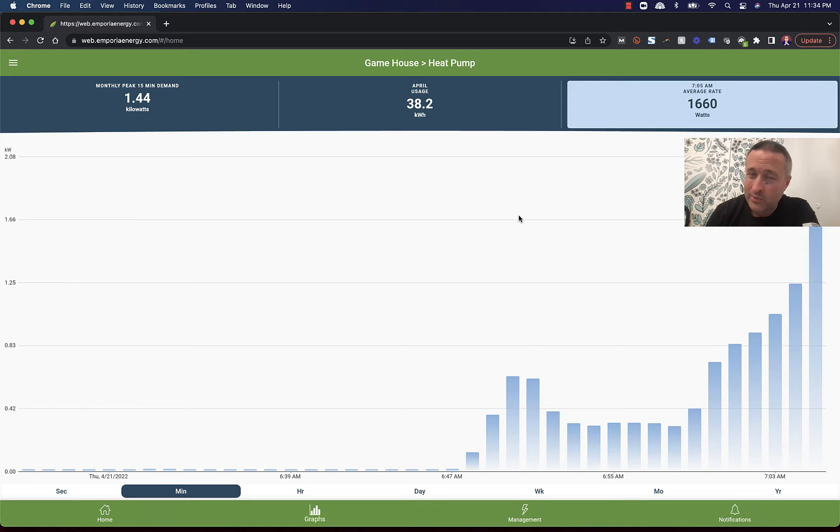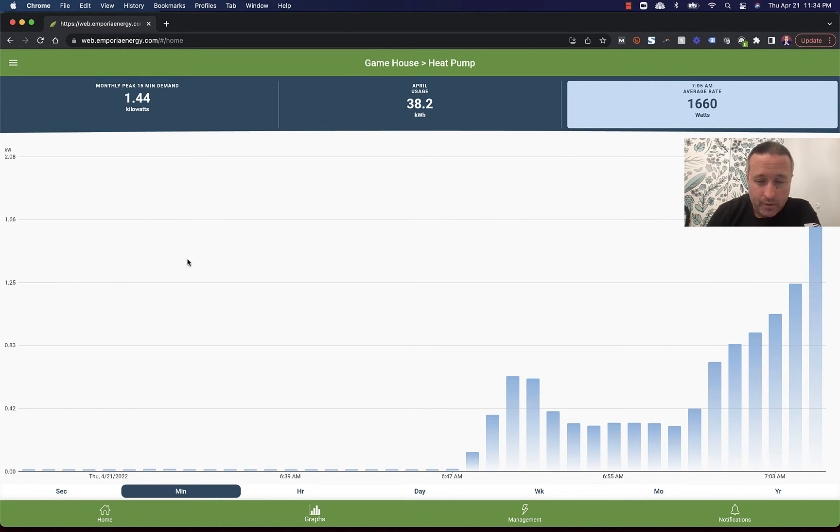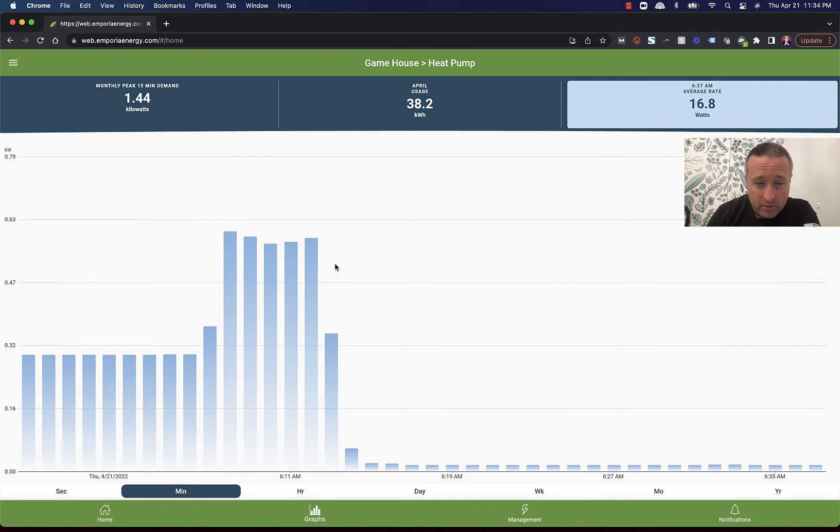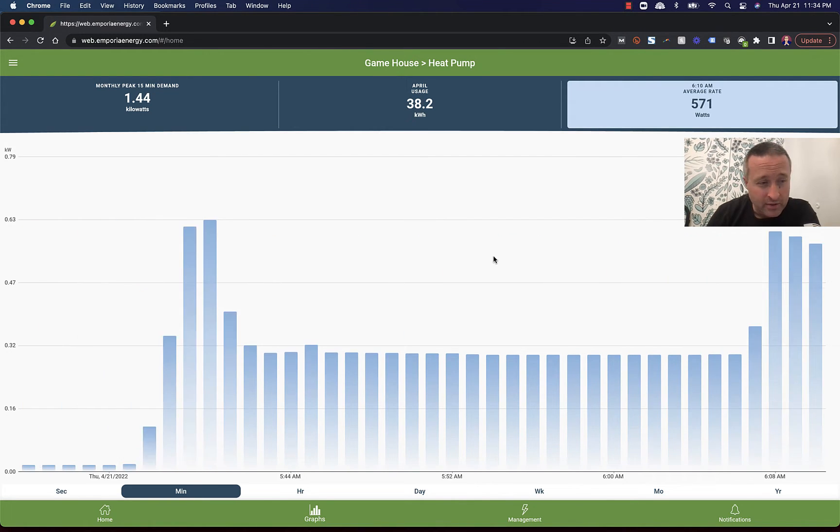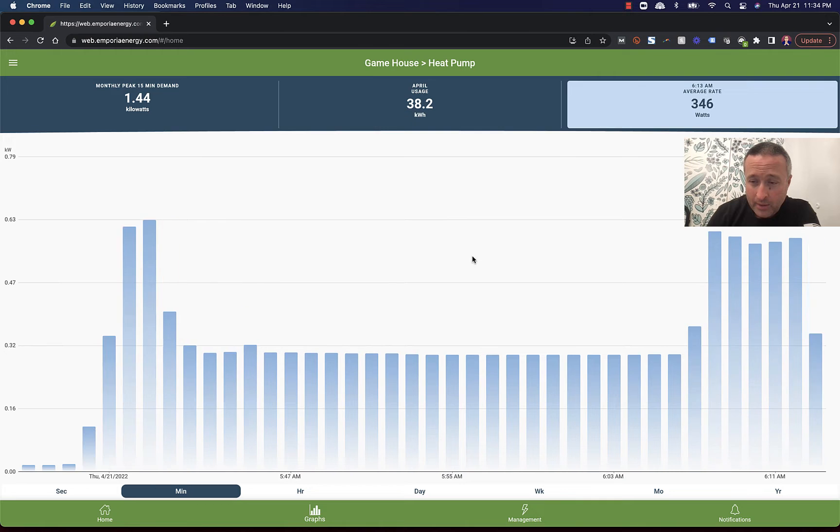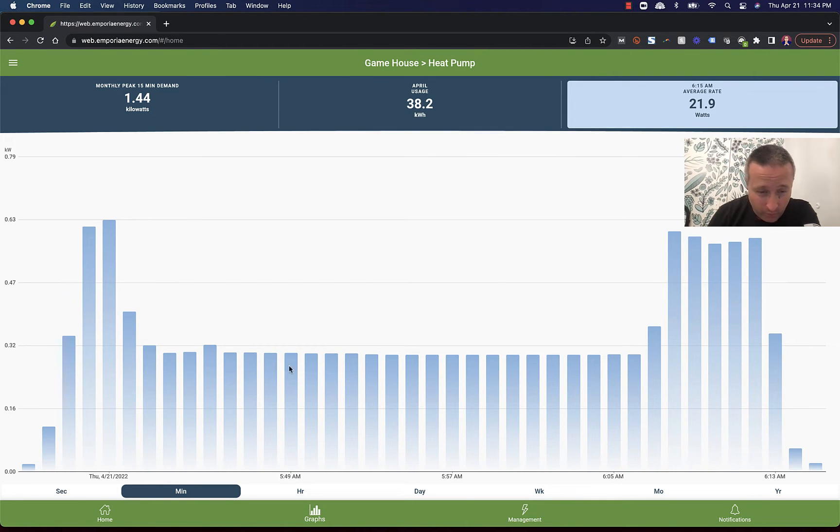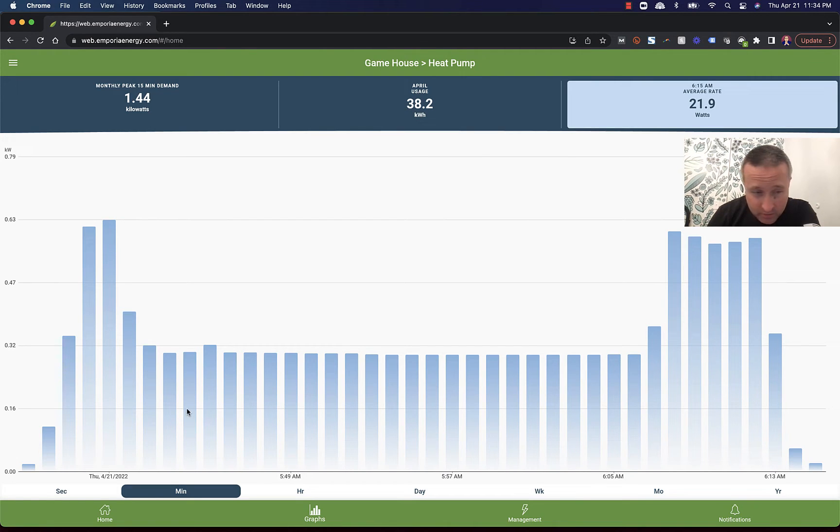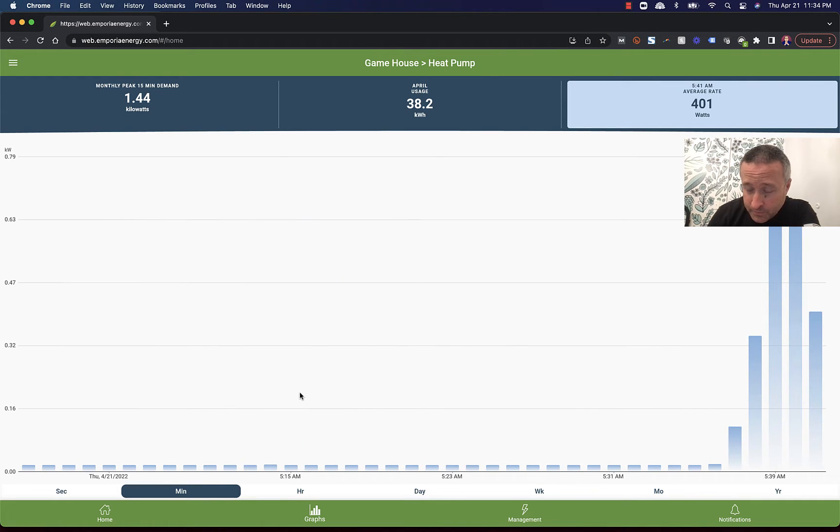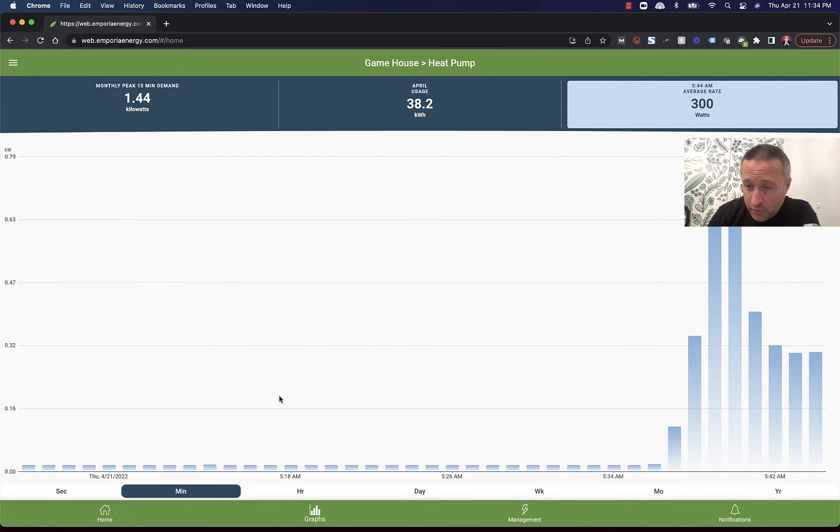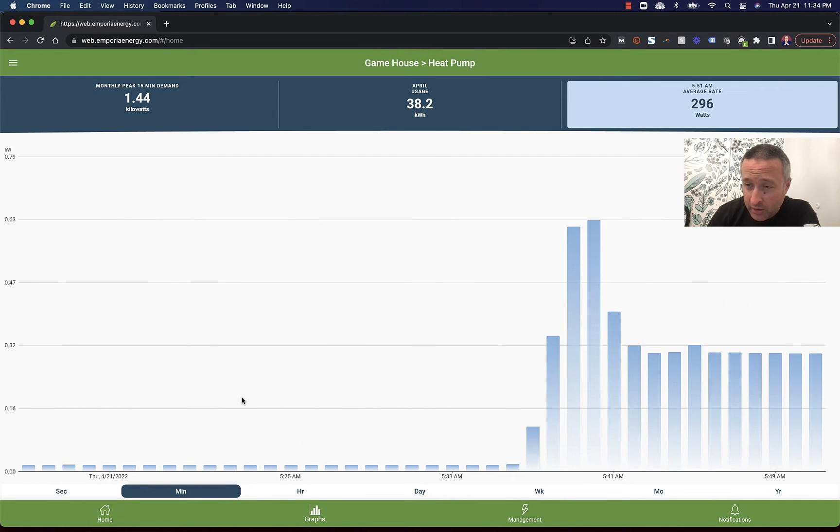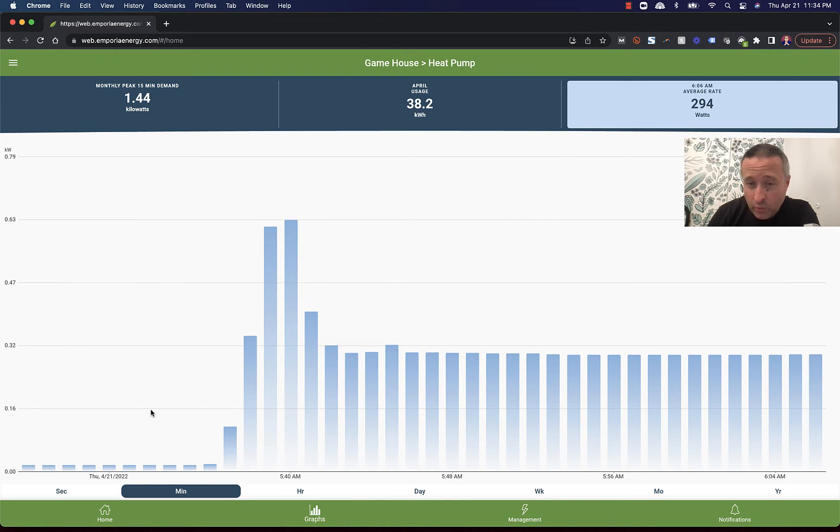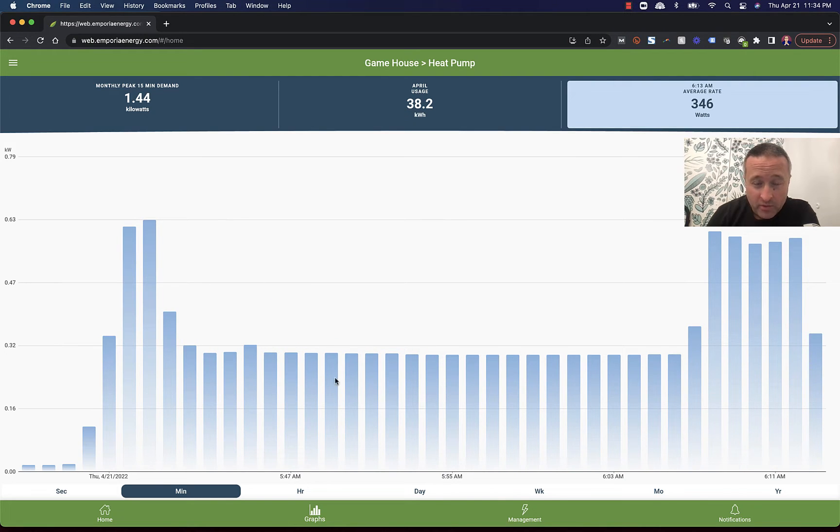It's a one and a half ton unit. So it can do a little bit more than one and a half tons, which makes sense. It's not really a one and a half ton compressor. It's got more. But let's keep scooting back. So it wasn't super cold last night, but it was a little bit. But note this here. See this nice flat line where it ran for quite a while. Let's see about what time it started.